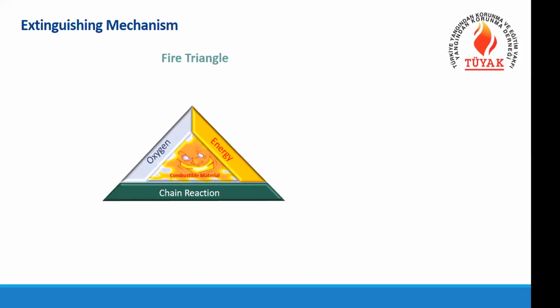We can use the gas suppression systems in any kind of fire situation, but we have limitations of these systems because of their high budget, and we cannot use them everywhere because of some physical restrictions. But for the fire types, class A, class B, and class C fires in general, we can use these gas systems. So we have a fire triangle that consists of oxygen, energy, and chain reaction, and the combustible material.